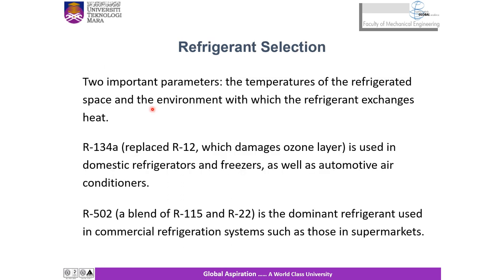To select a refrigerant, there are two important parameters you should pay attention to. One is the temperature of the refrigerated space. When the refrigerant expands in the expansion valve, the resulting temperature must be at least 10 degrees lower than the required temperature of the refrigerated space.